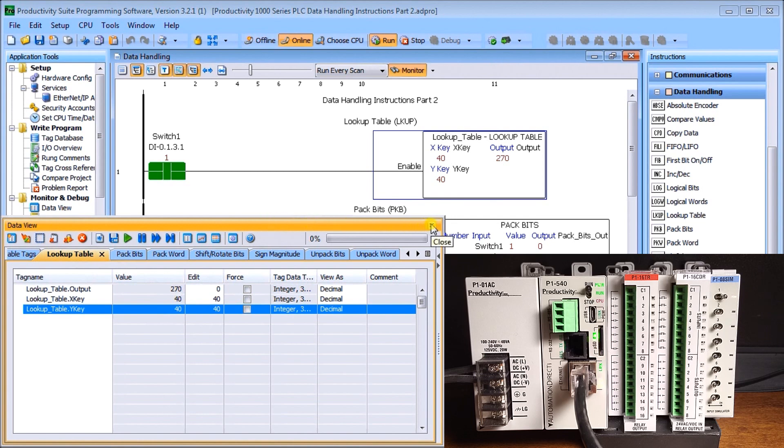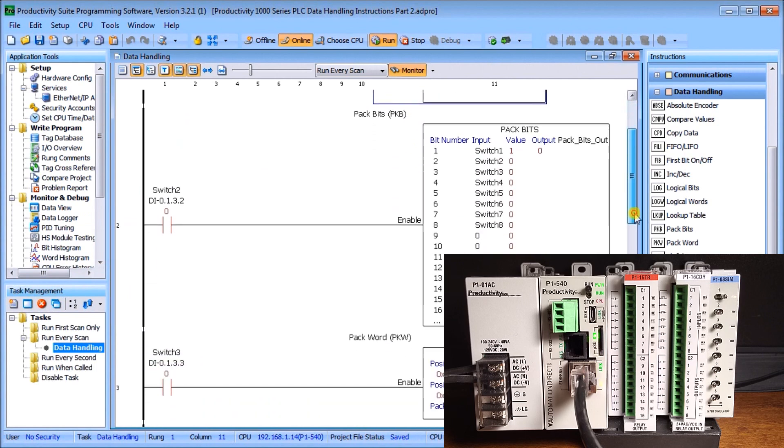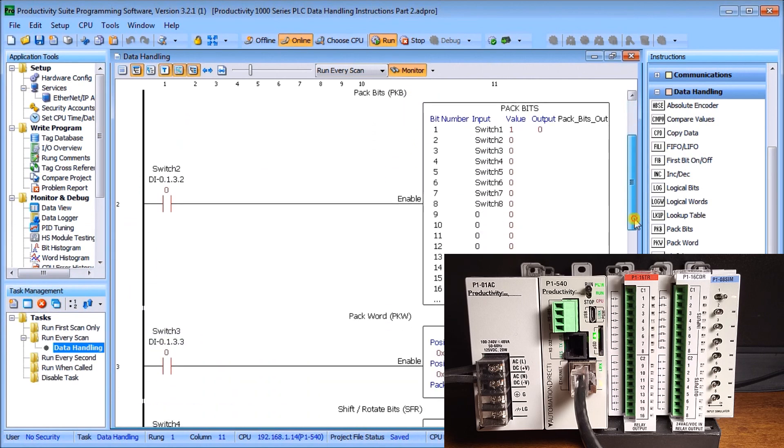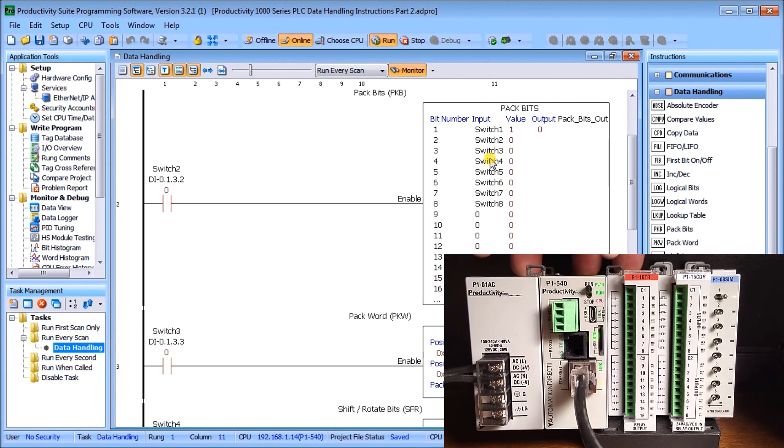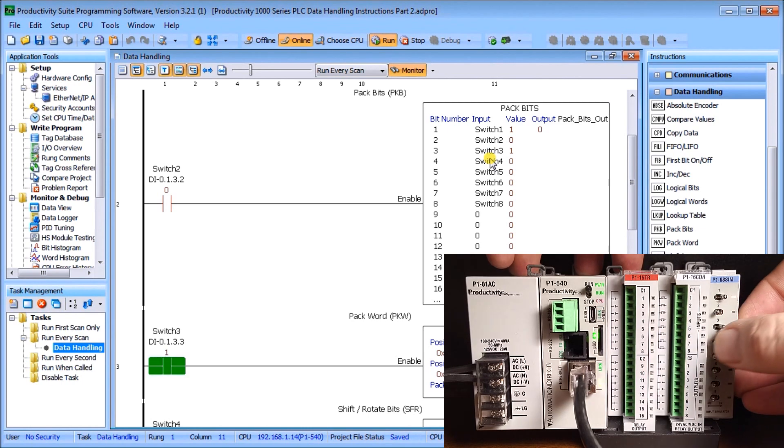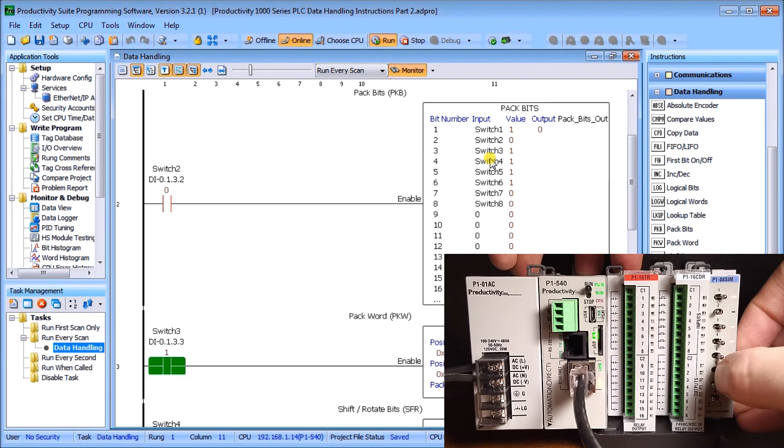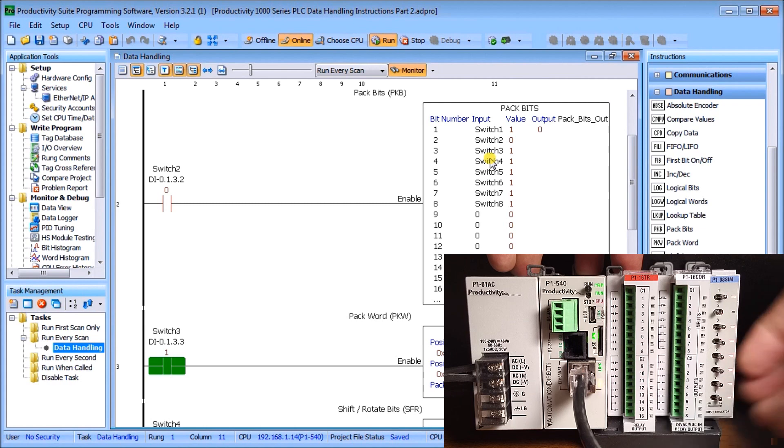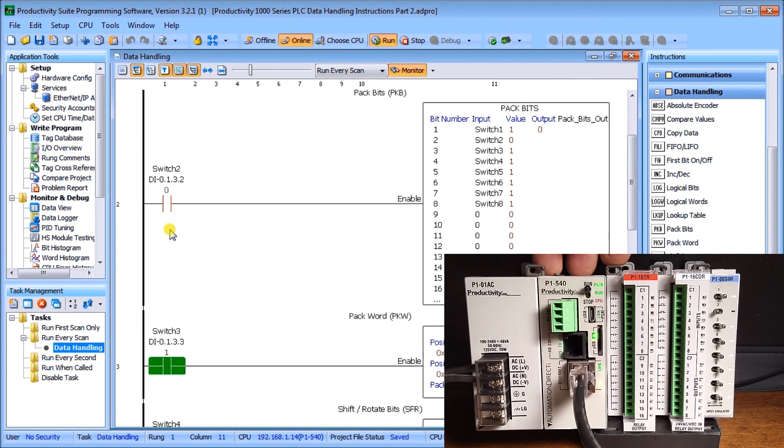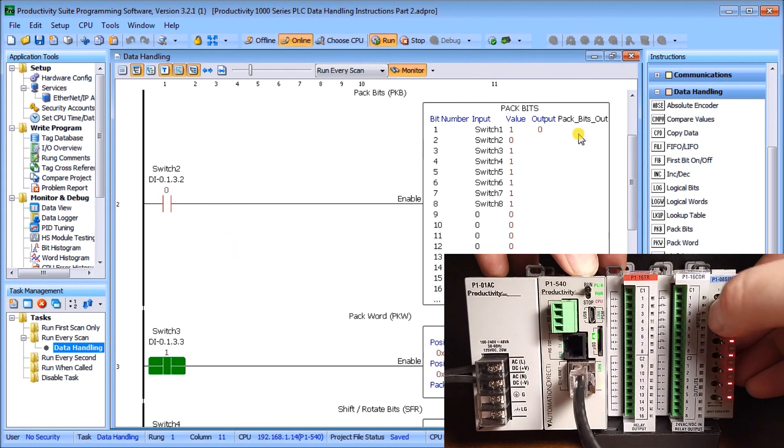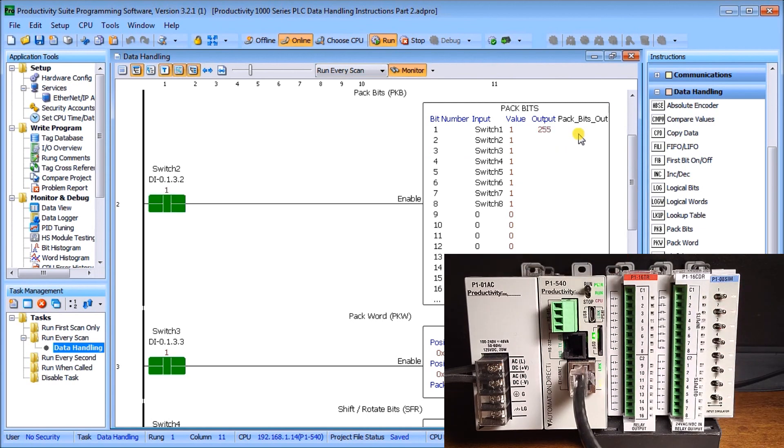The next one is pack bits. What this will do is take the bit numbers that we turn on. Currently we have switch number one on. Let's turn on a few of them here. We'll turn them all on actually. As soon as we switch number two on, it will pack that and put it on the output side. Sure enough, that's exactly what it did and it put the value of 255 into the output.